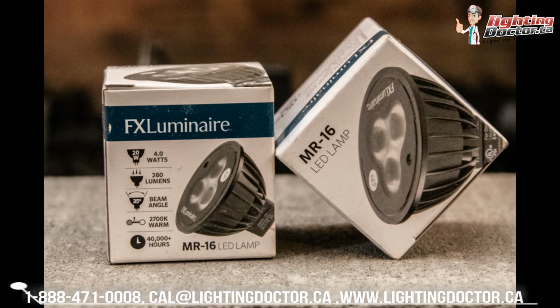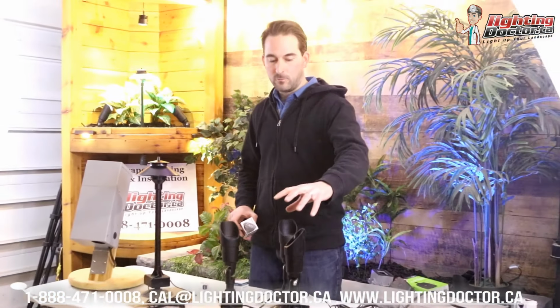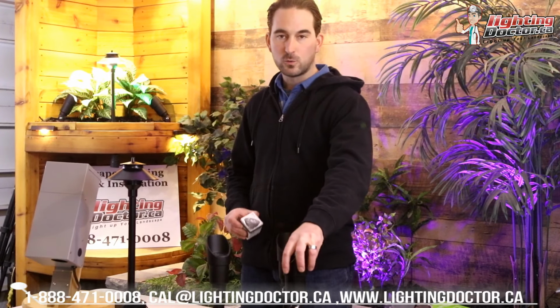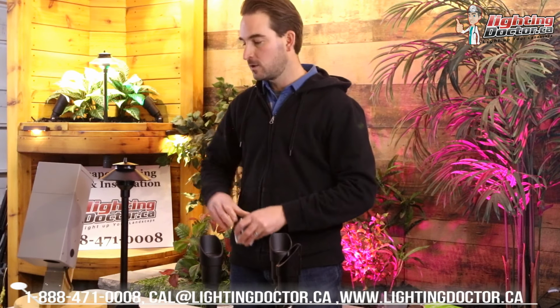So I have an example here. Say this was our system and we've got 3 accent lights. Each one is a 5-watt bulb, so 3 times 5 is 15 watts total. Then we've got our path light, which has a smaller bulb that's only going to use 2 watts. So we're at 15 plus 2, that's 17 watts. Really, all we need is a transformer that's approximately 20 watts or higher.